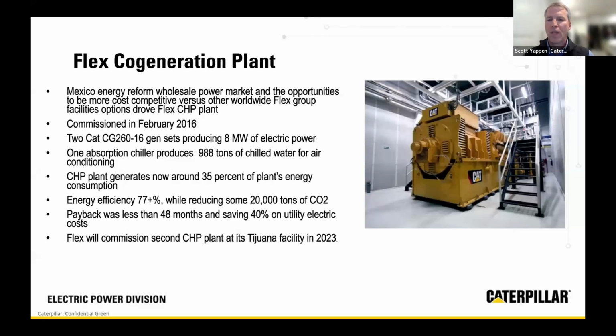The CHP design recovers waste heat from one of the engines at about 900 tons of chilled water, looking at around 10 to 10.4 degrees Celsius inlet and 7 degrees C outlet on the chilled water. There are plans to add a second chiller in the future and possibly an additional engine.